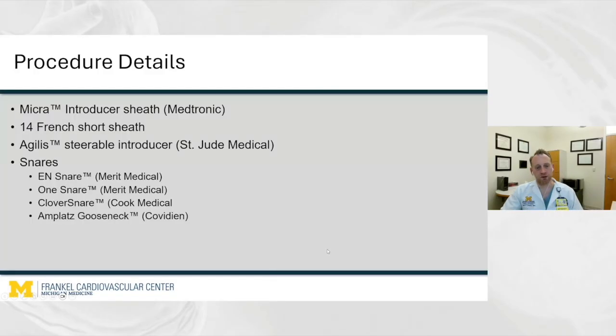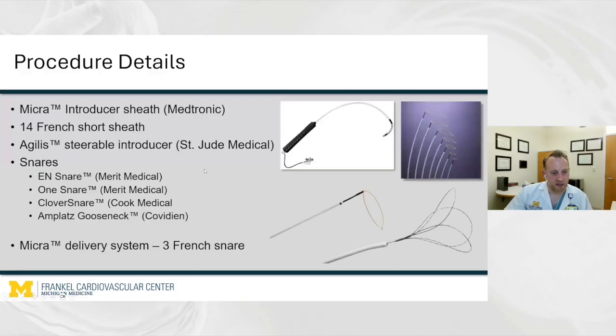So how do we do this? I briefly mentioned these different approaches. This is the most common approach. It uses the Micra introducer sheath in the right femoral vein. Through that, a 14 French short sheath, something 14, 16, 18, whatever you have available, something that's a step down from the Micra, 23 French inner diameter, and that'll allow the Agilis to fit through, because if you just put the Agilis in the Micra introducer sheath, you'll get feedback around the hemostatic valve. So this is just a step down, it doesn't have to be anything specific, it just has to fit the Agilis through it. And then through that, some snares.